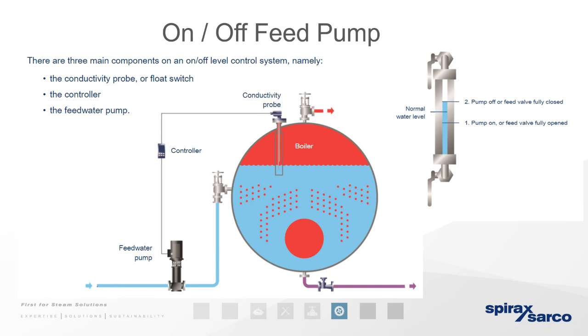On/off is cheap, easy to install, and good for smaller boilers. One pump boilers. Lots of starts and stops on the pump. So when we talk about start and stop, it's easier on smaller boilers because you don't see so much of a change. But the bigger the boiler, the more essential it is to have modulating control.